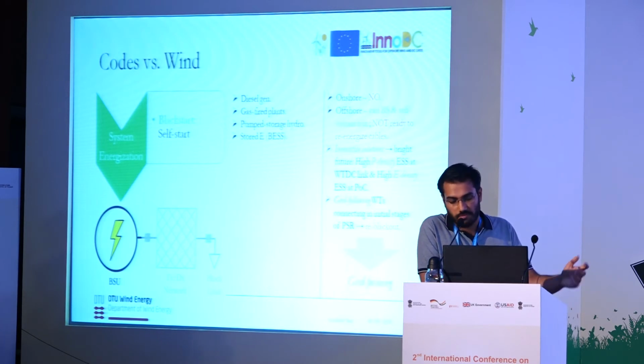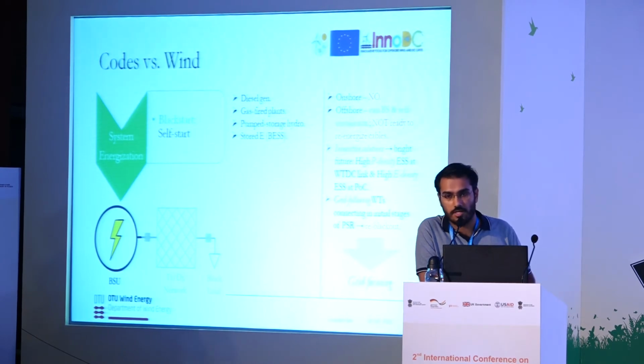The first is, as I talked about before, diesel is used for Blackstart. Onshore wind is not really a good candidate for power system restoration, mainly because of intermittency issues. However, offshore substations that have diesel generators, an auxiliary and a backup one, can Blackstart and self-sustain themselves. But right now, they are not technologically ready to re-energize the cables and deal with transients in a controlled manner. However, there are innovative solutions, for example, energy storage at the wind turbine DC link or the point of connection, that can provide some alleviation to risks that might come from intermittency or control problems.